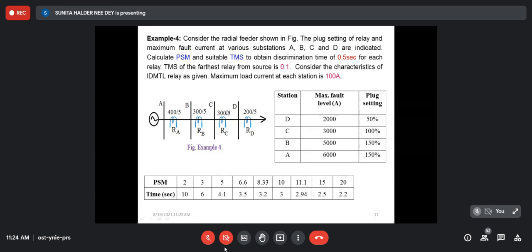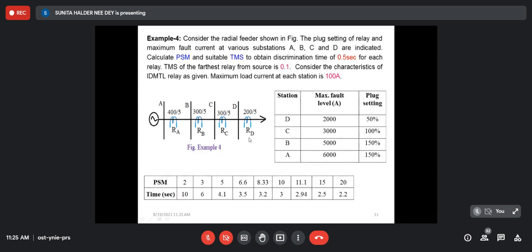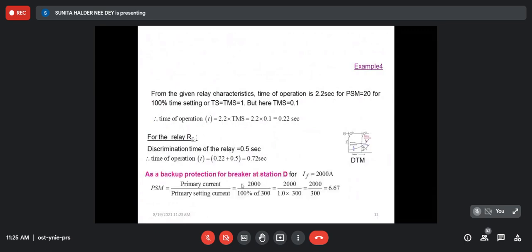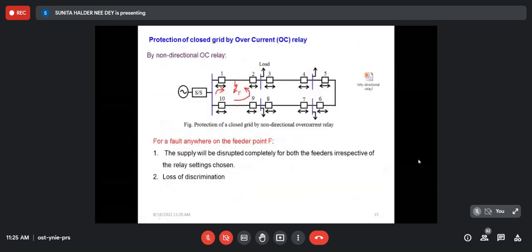In the case of a normal IDMTL relay, it can give protection over a particular current, but it cannot sense the direction of current. When sensing the direction of current is required, this type of relay is not suitable. This is a closed feeder or a feeder with both-end feeding. If there are different sections with loads at every bus and different segments of transmission lines — called feeders — the non-directional overcurrent relays cannot sense current direction.